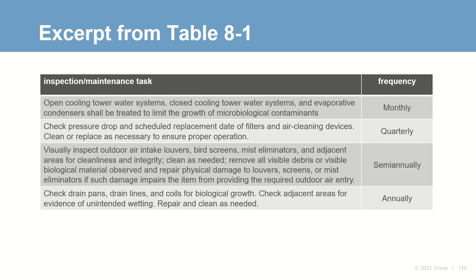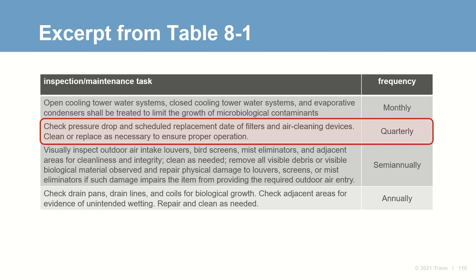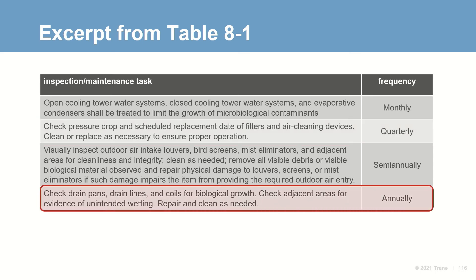Here's an excerpt from that table listing just a few of the inspection and maintenance tasks. For example, at least once every quarter you should check filters and replace them if necessary. And at least once a year you should inspect drain pans and coils and clean them as needed.